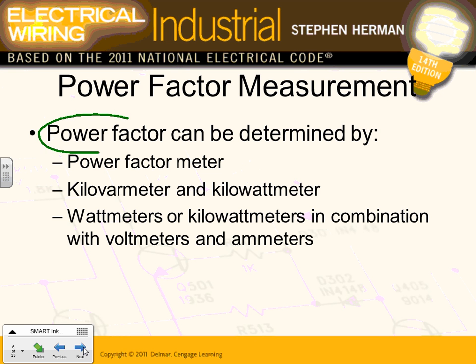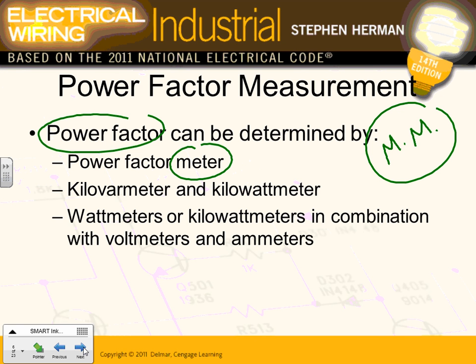So how do you measure the power factor? You can have a power factor meter. But most of the time, guys, with a multi-function meter or digital meter, you have one meter that can give you kilowatt hour, VARs, power factor. You can get the harmonics out of it. You can get the current, the voltage. That's what customers do if you go in a hospital or a sport arena. Inside your switchgear, the owners will specify a multi-function meter, just one meter. Square D and all those manufacturers have their own brand of it. It can give you everything you need to know about your power system: what's the voltage, what's the current at every moment, what's the power, what's the kilowatt so far, what's the VAR, what's your power factor, what's your harmonics, and the level of your harmonics.